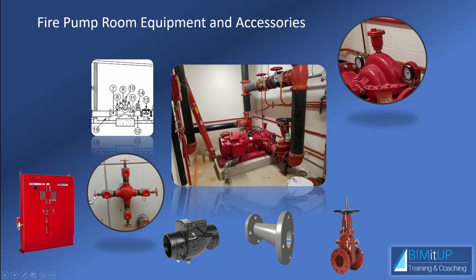You obviously need a fire pump controller, which is gonna set up the starting and stopping of the fire pump. Those typically are accompanied by an ATS, which is an automatic transfer switch, and that's gonna dictate whenever you lose regular power, how to switch to emergency power.